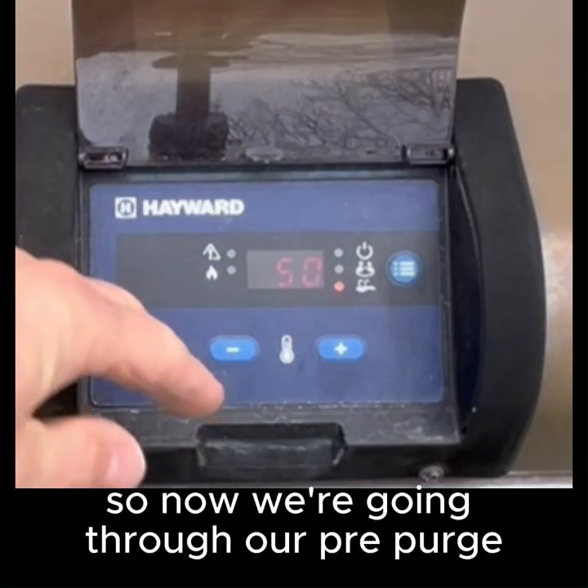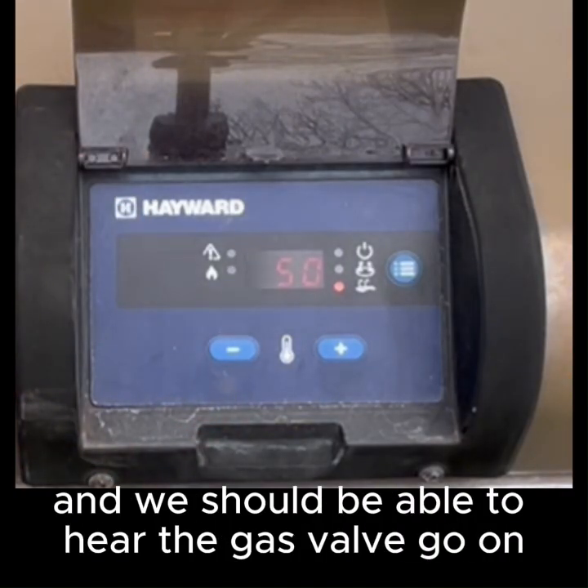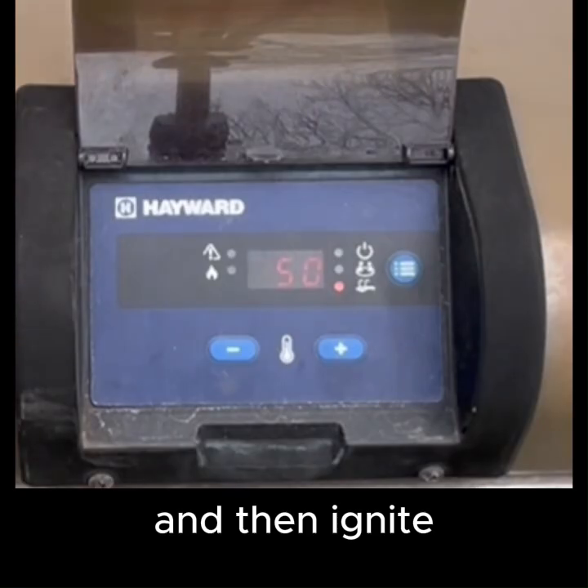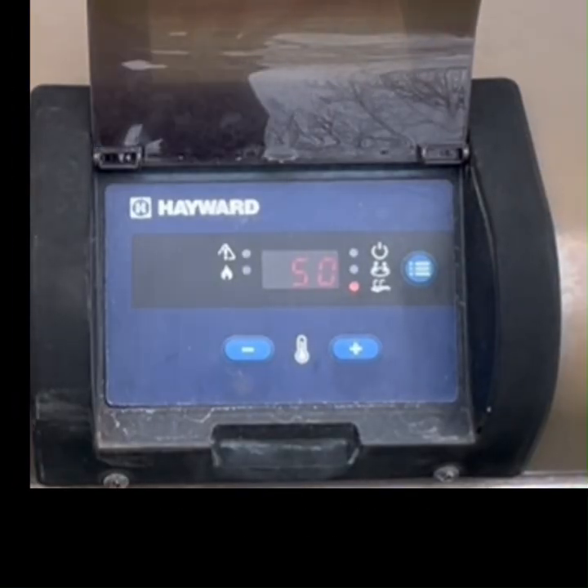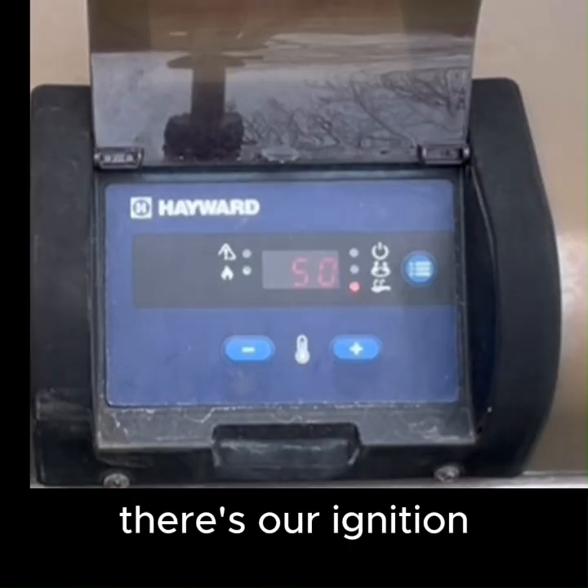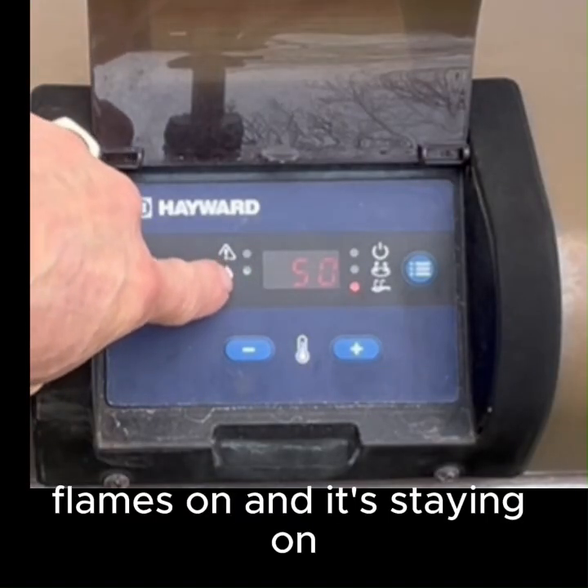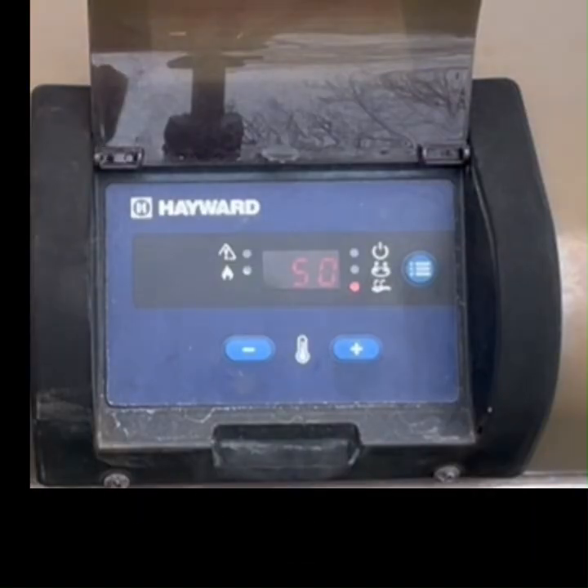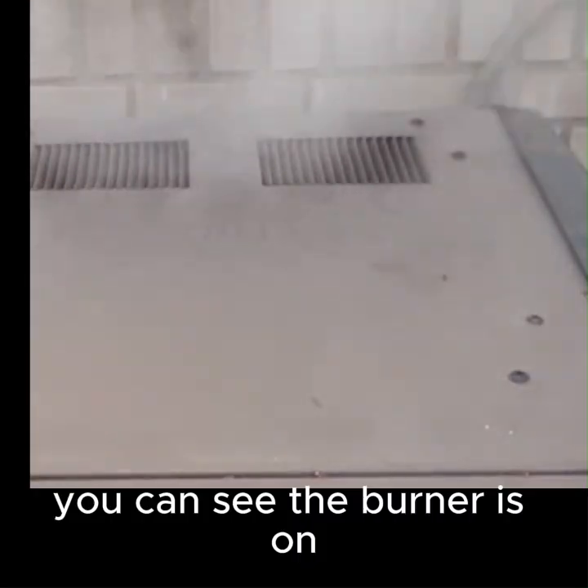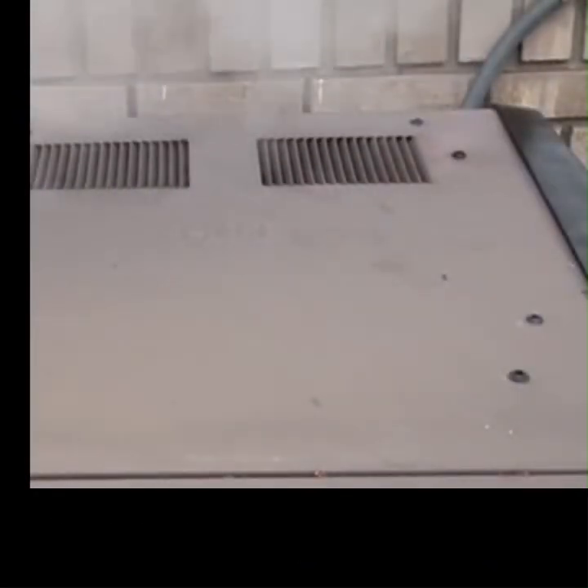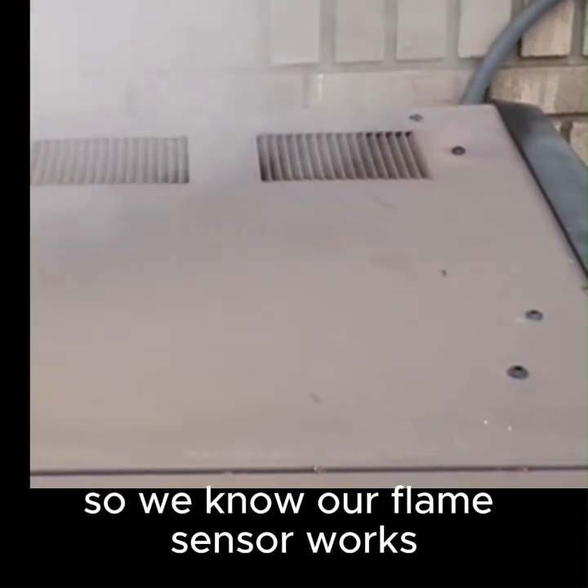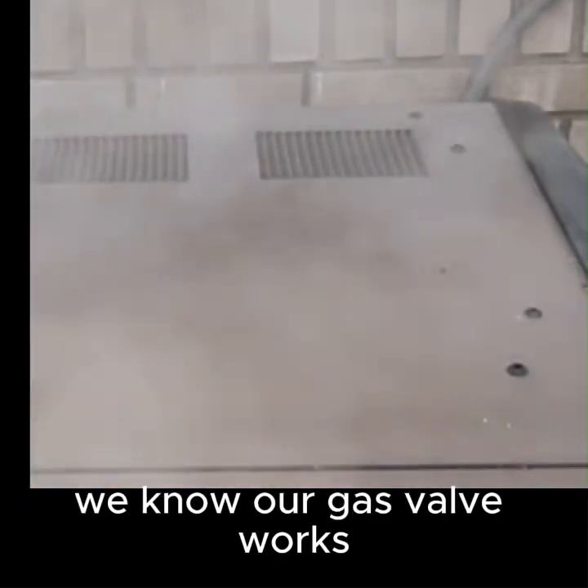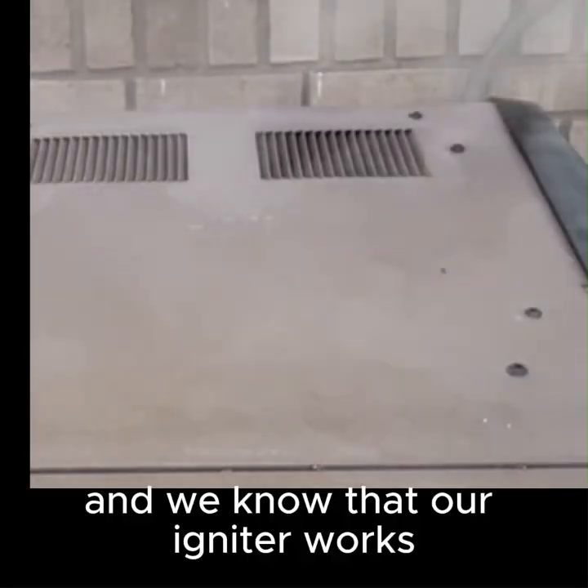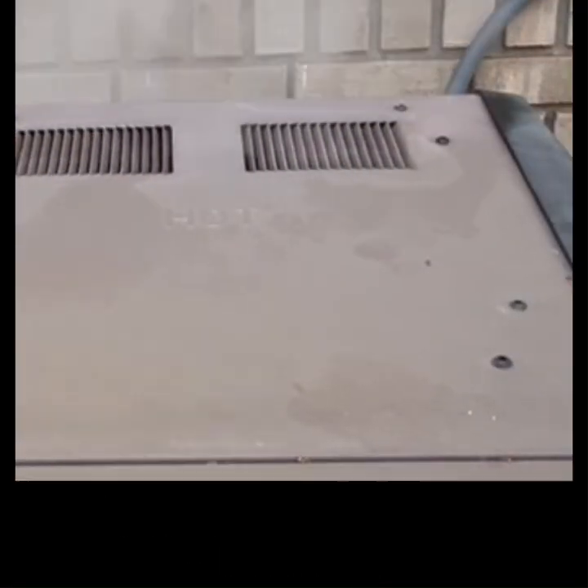So now we're going through our pre-purge, and we should be able to hear the gas valve go on and then ignite. There's our ignition. Flames on, and it's staying on. And if you look, you can see the burner is on. So we know our flame sensor works, we know our gas valve works, and we know that our igniter works. But we're going to do a little bit of deeper checking on some of that other stuff.